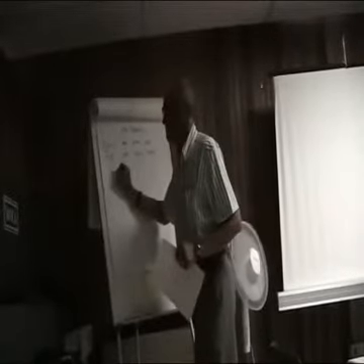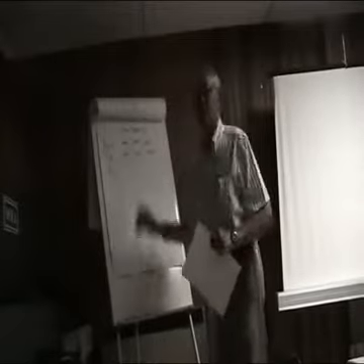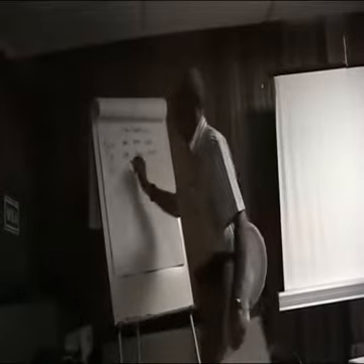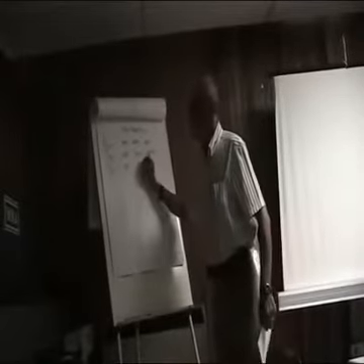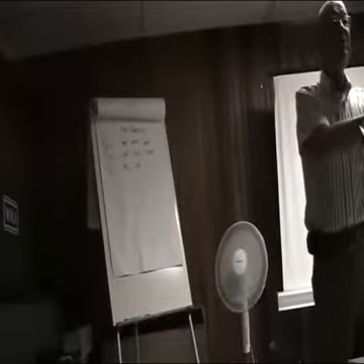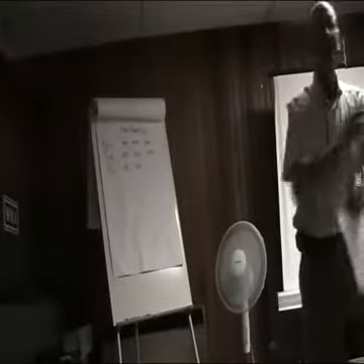Same with your pressure drop. At maximum flow, your valve is fully open, you have a very low drop over your valve, you have a wide opening. So what you'll find is here, it'll be 50 kPa. At normal flow it will be 60 kPa, and then at minimum flow, because the valve is closed, you have a high back pressure and you have a very small downstream pressure. So your pressure drop is much higher, and this is where you normally pick up your problems with cavitation and noise and those kind of things.